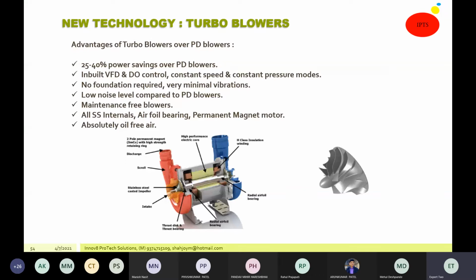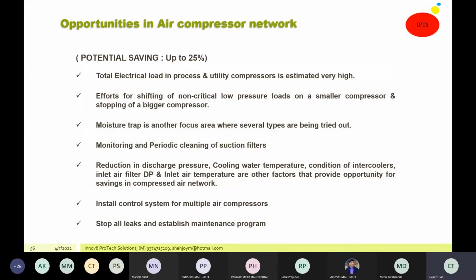Air compressor. Say every industry has an air compressor network, and they have multiple air compressors and a very complex air network. It can be plant air or instrument air or maybe any other type of air, and there is always a potential saving of up to 25% energy by proper loading of the compressors, reducing the leaks, and stopping the non-critical low pressure load and providing small compressors, low head compressors for the non-critical low pressure load. Moisture trap in the compressor.